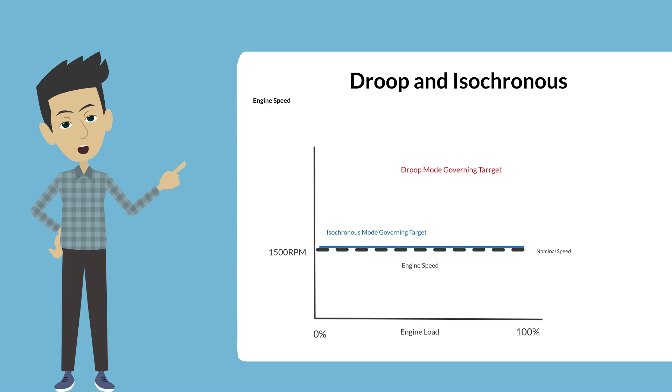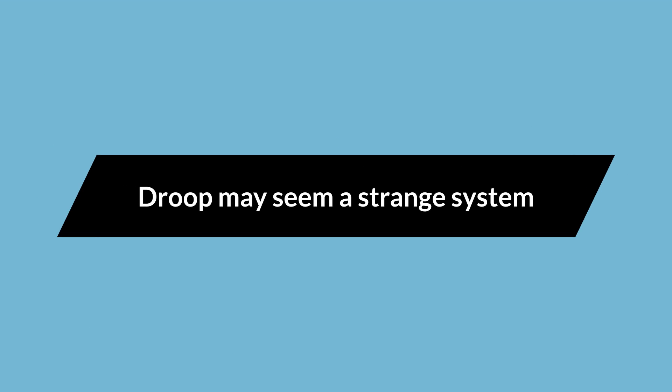In droop mode, the governor only targets to be at the nominal 1500 rpm speed at full load. At no load, the speed will be typically 5% higher. As the load increases, the speed falls proportionally down to 1500 rpm as shown on this graph. Droop may seem like a strange system.